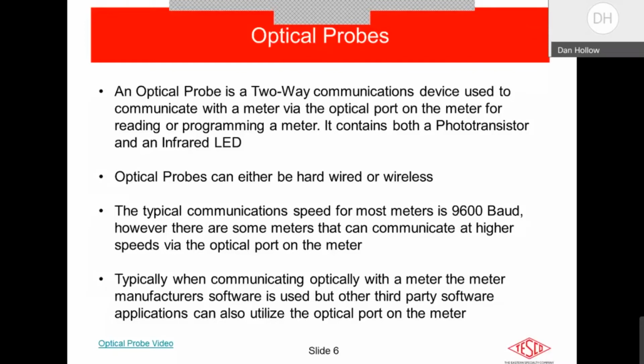And also things like alarm conditions. A lot of meters are set up to generate alarms if they see a voltage sag or a voltage swell or a total harmonic distortion threshold exceeded. So all of the data that's in that meter can be extracted through the optical port using the meter manufacturer's software, whereas typically some or a good number of the AMI systems on the market today just retrieve a subset of the data stored in the meter rather than absolutely everything. When you read it with the meter manufacturer's software optically, you're going to get absolutely all the data stored in that meter. Let's go ahead and run that video there, the probe.